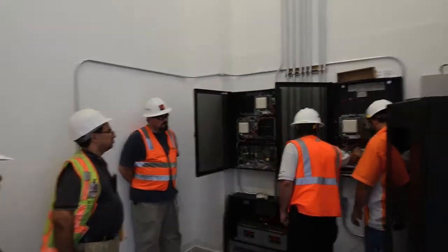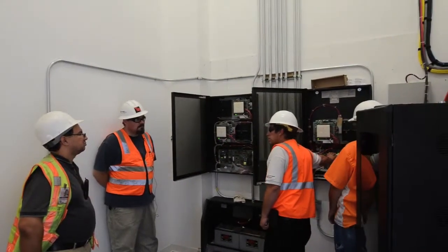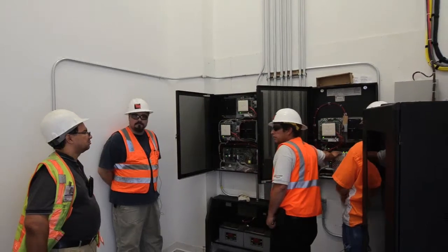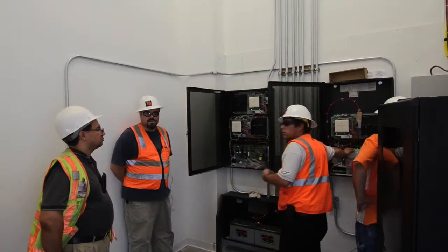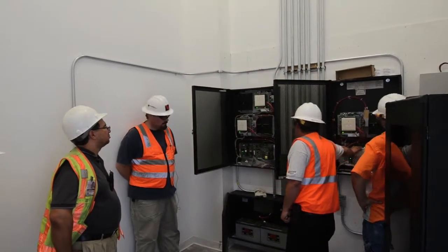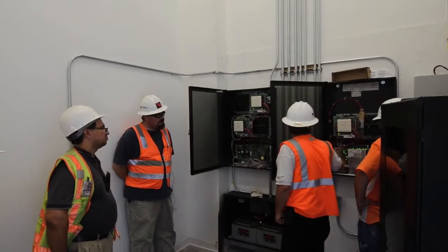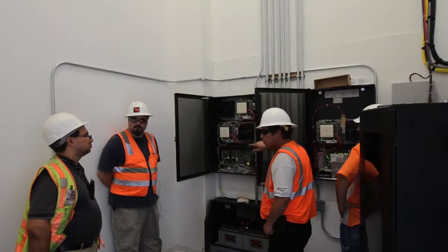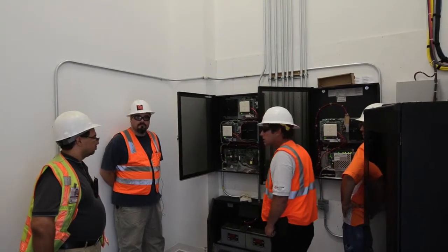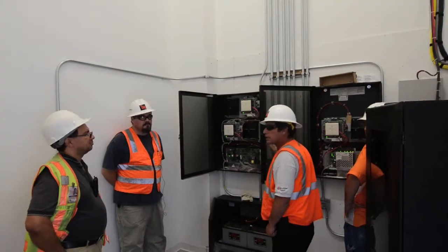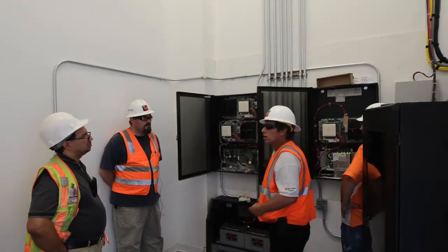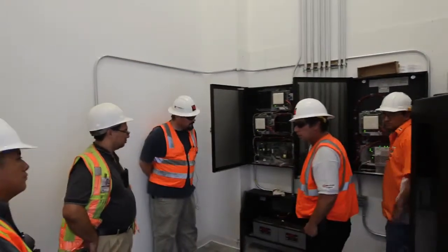However, we've opted to use the main power supply here, which will monitor the voltage and monitor any troubles, and trickle charge it, differential voltage on the batteries, over amperage. And this is actually responsible for charging and providing backup power to all the power supplies as well as charging the batteries. And it's the same thing on the other IDF. Right. And then the main panel also has its own set of big batteries as well upstairs.